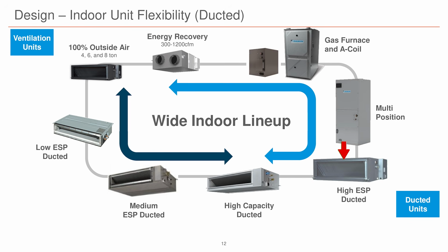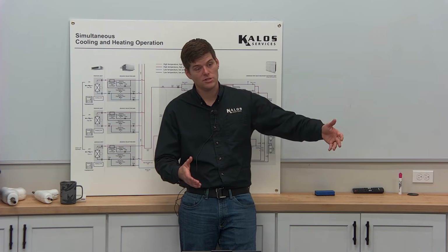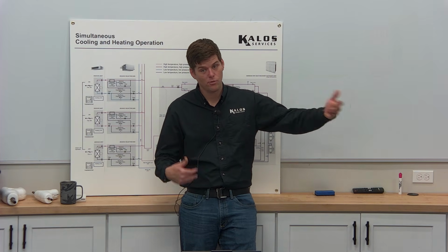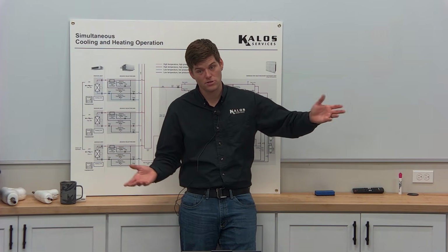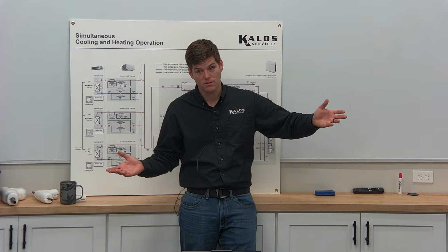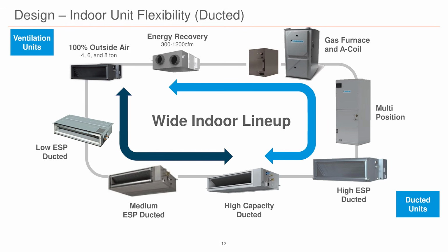I'm sure we've seen some mini splits like that, right? They have a high, medium, low static unit, right? We don't ever install the low static because it's completely useless. Everybody gets the low static unit because of cost, and then they put like 40 feet of ductwork on it, and it literally just grows mold because it can't perform.